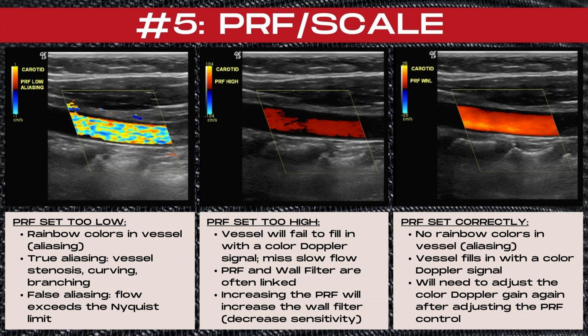Aliasing can also represent true velocities, such as within an area of vessel curvature or narrowing, or when flow velocities become turbulent and increase in velocity. Causes of false aliasing are the use of angles over 60 degrees or a PRF that's set too low. Ultrasound pulses are transmitted at a certain frequency, and the number of pulses of sound that occur in one second is the PRF or pulse repetition frequency. The PRF or scale control increases or decreases the range of velocities the ultrasound machine can detect and changes the range of velocities displayed on the color Doppler map. In the scenario to the left, the PRF is set too low and you're going to see rainbow colors within the vessel — this is aliasing.